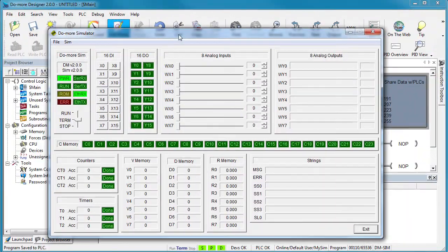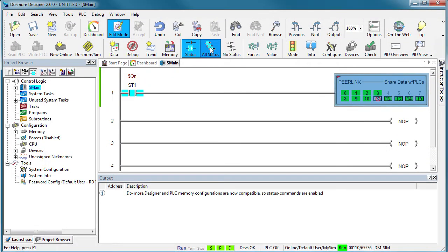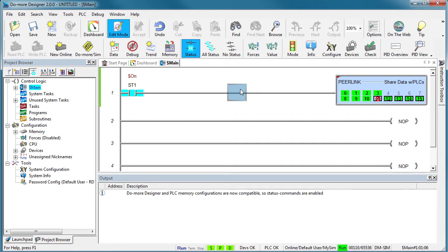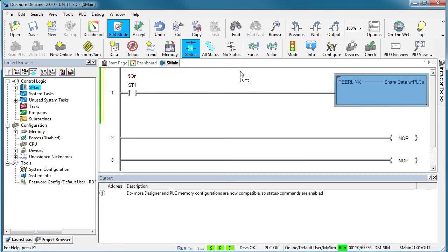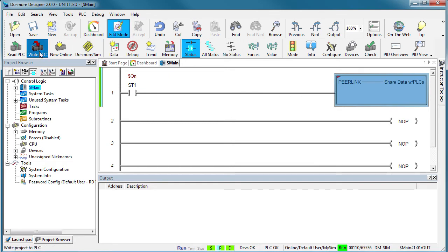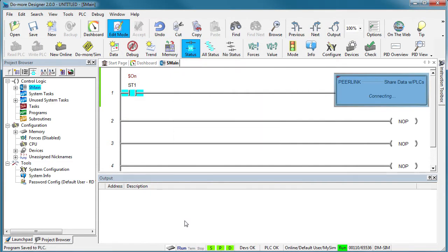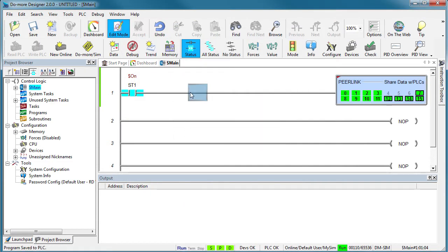Write it to the PLC. Make sure the PLC is in run mode and enable status. Ah, look at that. This PLC is trying to control these five blocks of memory. But there is a conflict with this block. Someone else is trying to use it. We know that. So let's change this PLC to use these five blocks. Accept it. Write it out. Voila. Everybody is happy again.